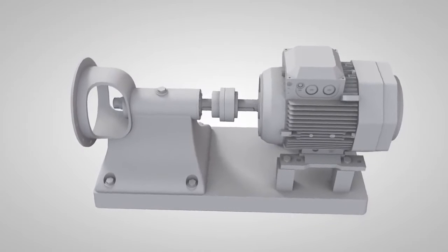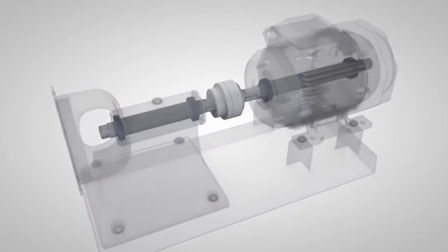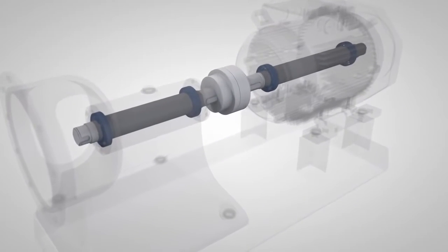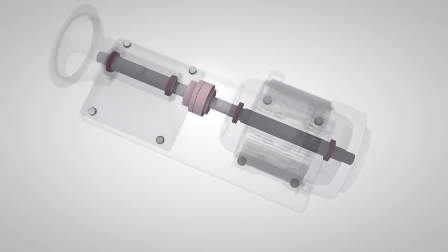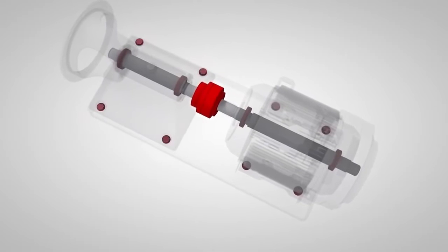Correct shaft alignment is very important for your machines, as misalignment causes vibration and additional forces that damage your machine components, such as bearings, seals, couplings, and foundation bolts.